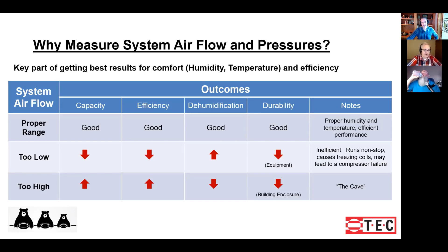Let me just mention one more thing. So there is a case where you want that high airflow, and that's if you're in a dry climate. If you're in Arizona, there's no reason to do much dehumidification. And so designing the system for very high airflow is a good way to get extra capacity and extra efficiency.